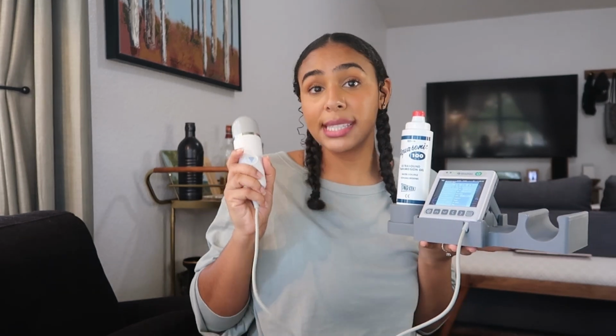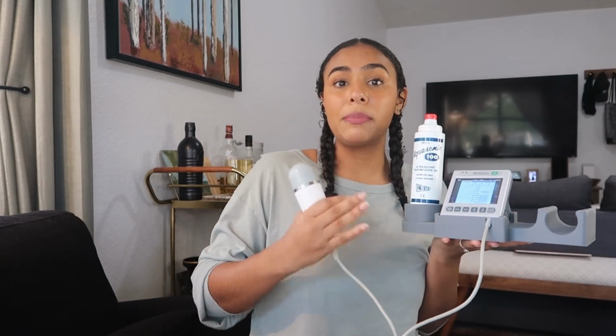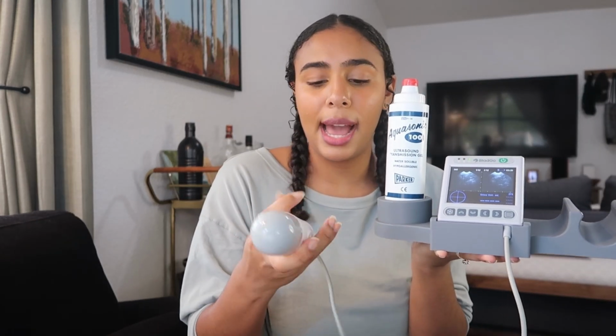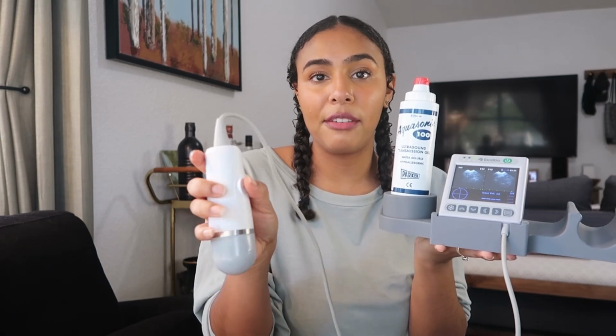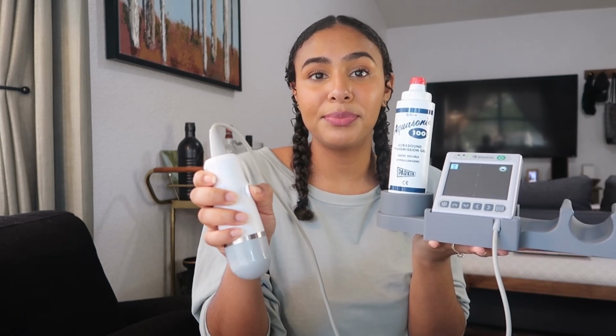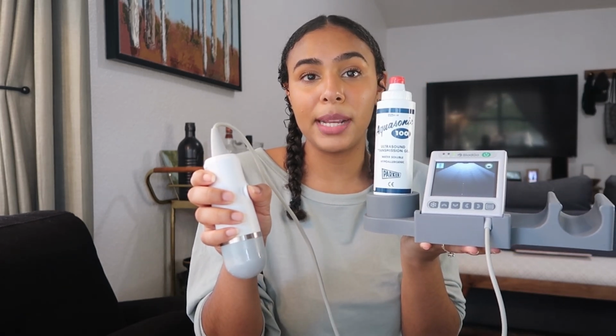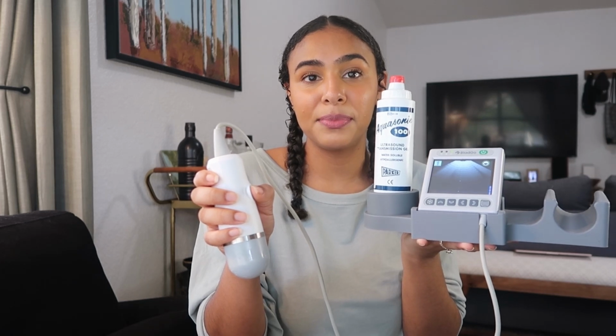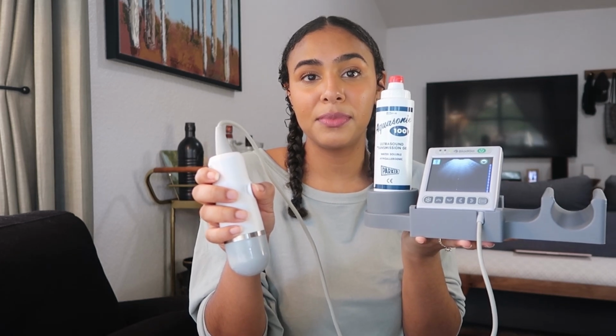Another thing that's really cool with this device is it actually has a button on the probe for you to start scanning and to take that automated measurement. So you can either click this button while you're scanning, or you can click your freeze button here to begin your automated scan. So I'll show you what that looks like. Here I'm going to use it on the actual probe itself. So say I'm scanning and I find my perfect placement, I just click, and you can see on the monitor it begins scanning. And it gives you your results.